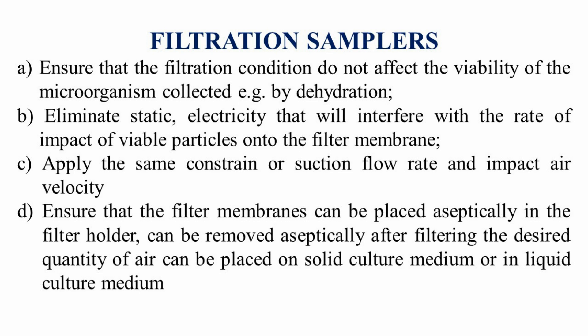Factor B: eliminate static electricity that will interfere with the rate of impact of viable particles onto the filter membrane — static or electric charge should not interfere with the sampling method and viable particle impaction. Factor C: apply the same constraints on suction flow rate and impact air velocity — the sampling rate and impact velocity should be appropriate. Factor D: ensure that the filter membranes can be placed aseptically in the filter holder, removed aseptically after filtering the desired quantity of air, and placed on solid or liquid culture medium.